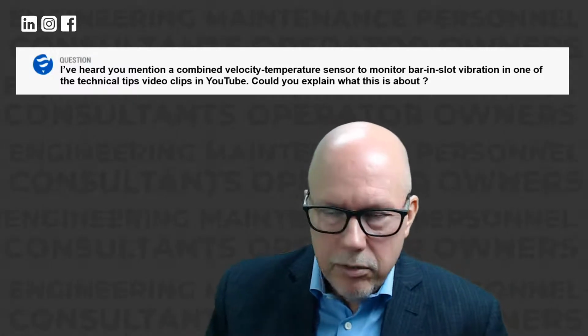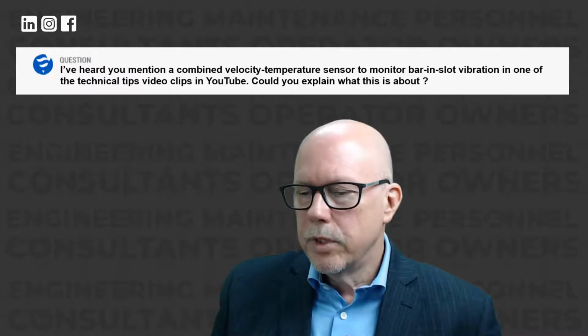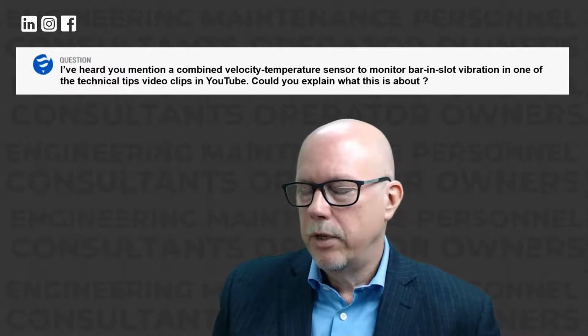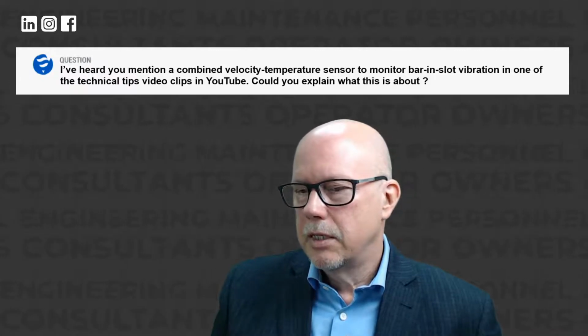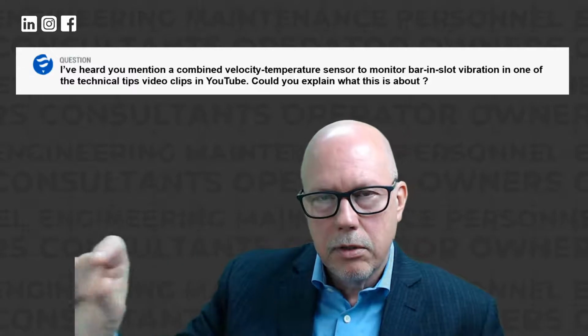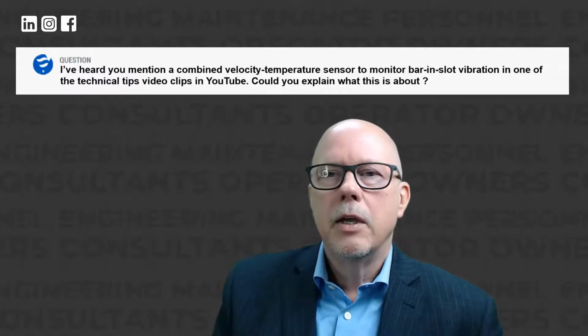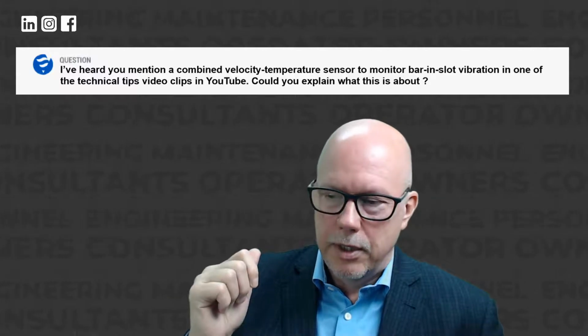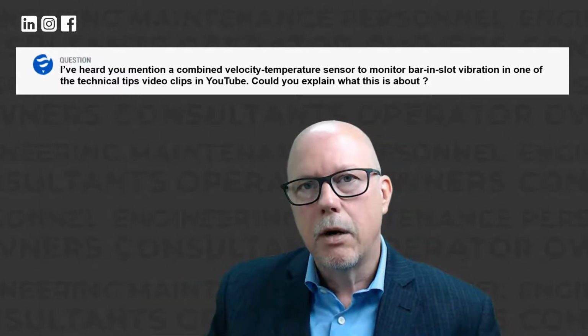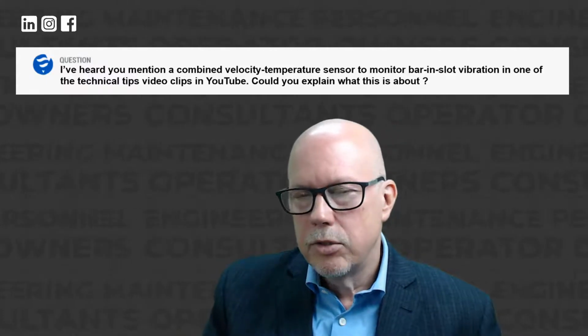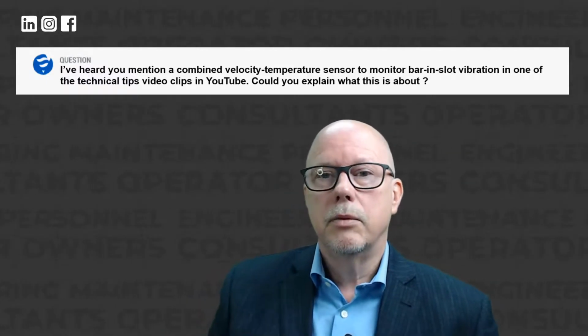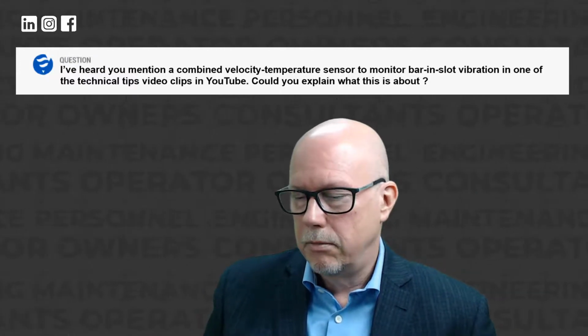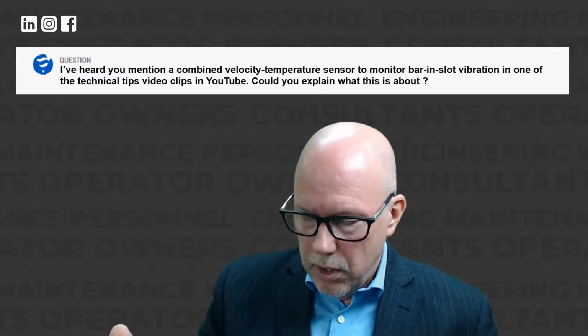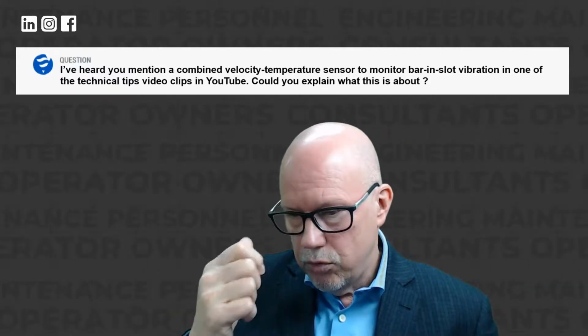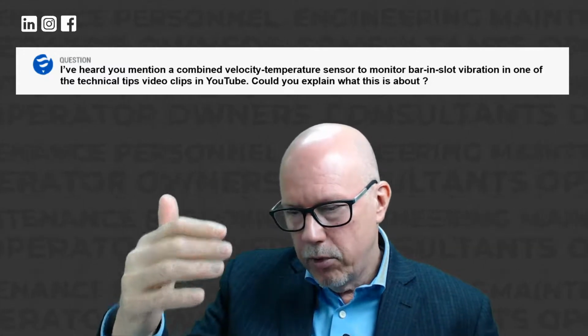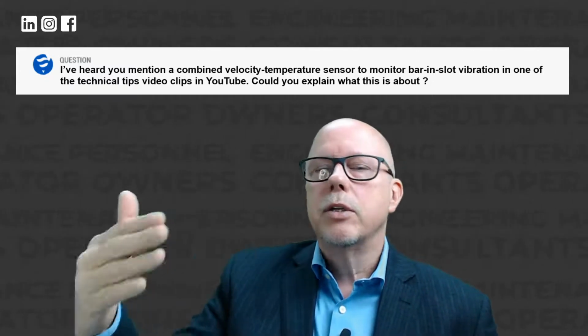We worked around it, trying to find the best coverage possible. To resolve this, our R&D department came up with a new sensor—basically a series of 100 sensors on a communication line. These sensors provide the absolute vibration and temperature of the bar, so you can cover all the bars in a much more cost-efficient manner, and output either acceleration or velocity, whichever you choose, along with temperature.